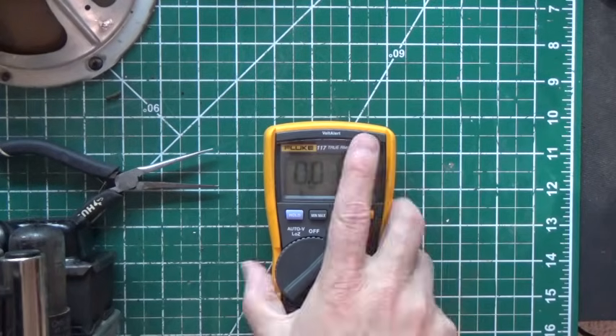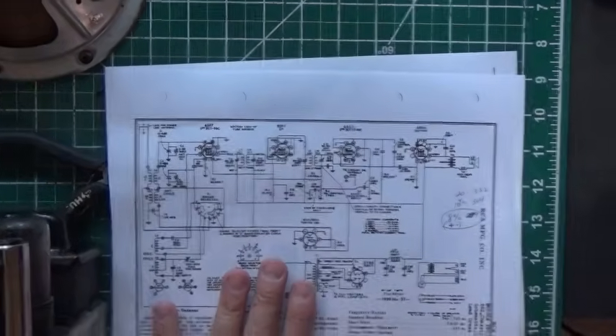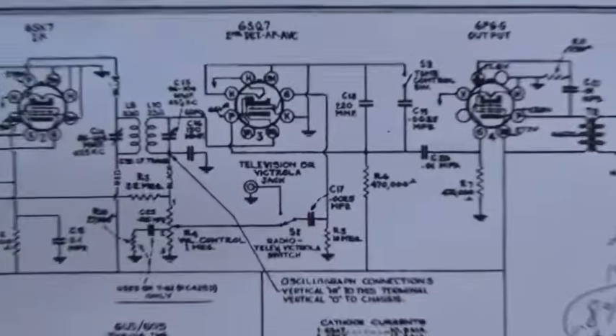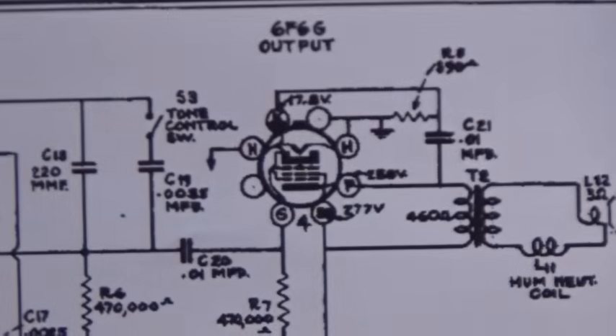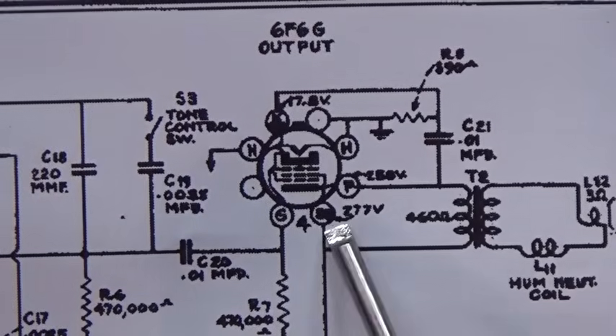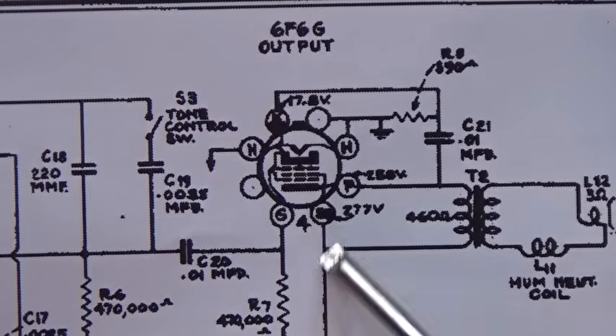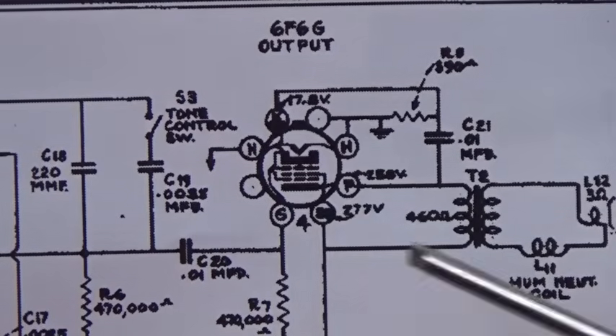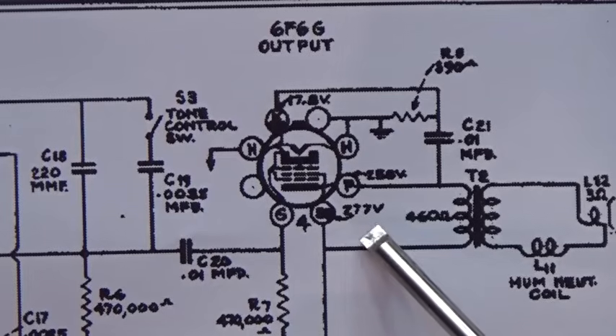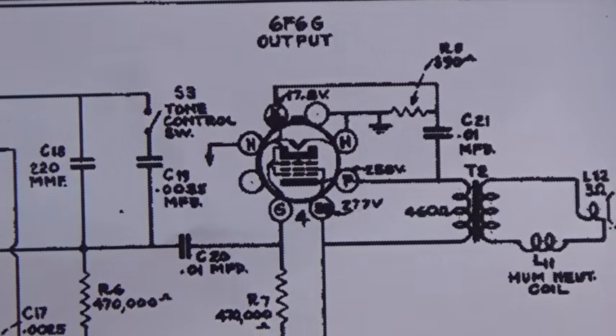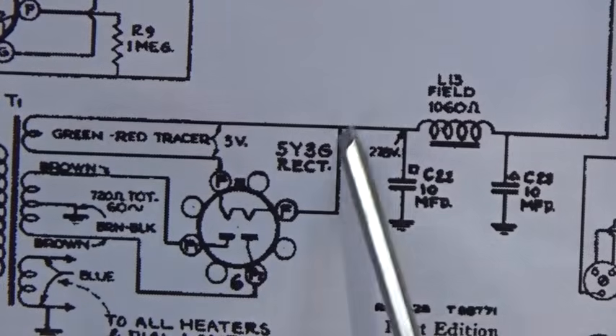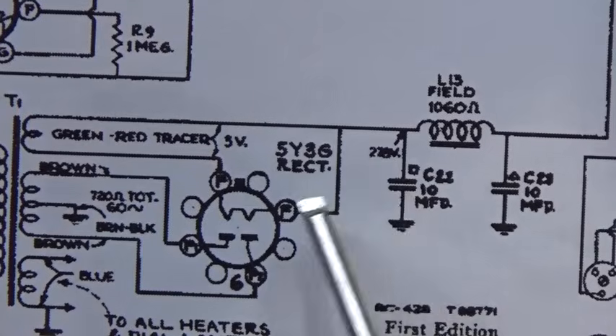Okay, why is that 300 volts important? Let me explain. Take a look at our schematic, let's zoom in so you can see it. You'll see right here off our rectifier, coming up here, this comes off of our filter caps. You'll see that the radio is calling for 277 volts. Similarly, if you look here, coming right off of the rectifier, it's mentioning 277 volts here as well.